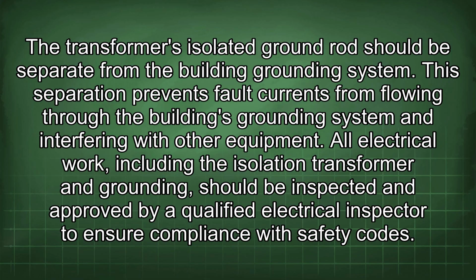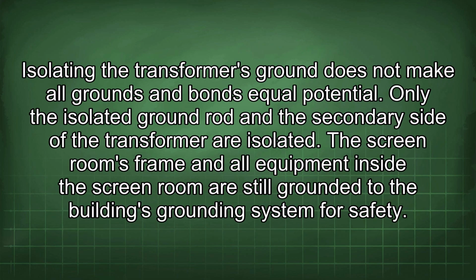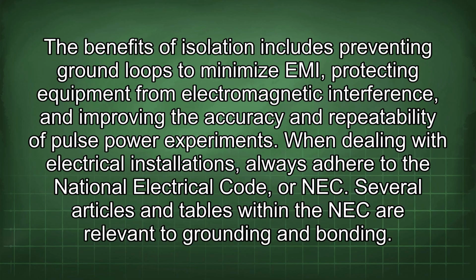All electrical work, including the isolation transformer and grounding, should be inspected and approved by a qualified electrical inspector to ensure compliance with safety codes. Isolating the transformer's ground does not make all grounds and bonds equal potential. Only the isolated ground rod and the secondary side of the transformer are isolated. The screen room's frame and all equipment inside the screen room are still grounded to the building's grounding system for safety. The benefits of isolation include preventing ground loops to minimize EMI, protecting equipment from electromagnetic interference, and improving the accuracy and repeatability of pulse power experiments.